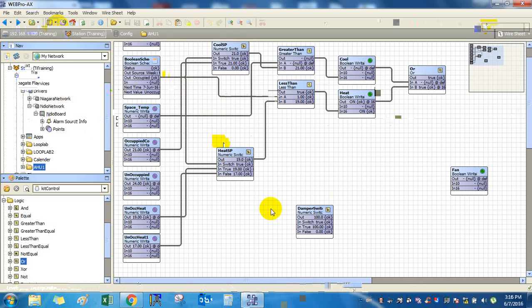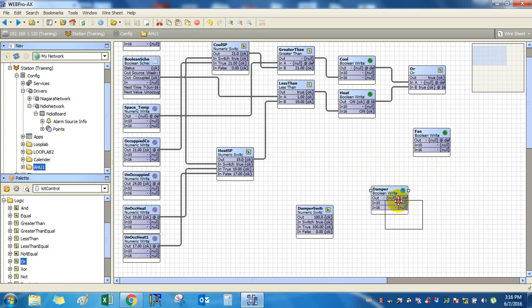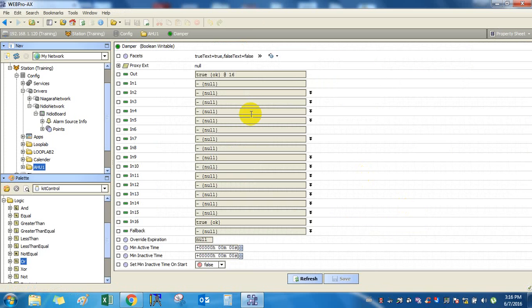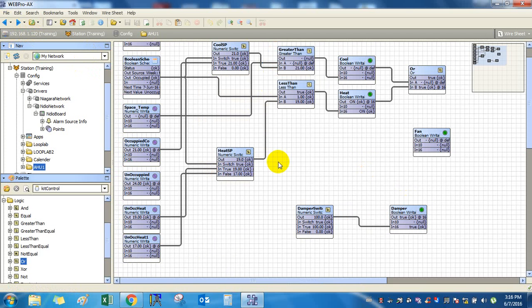Then add another numeric writable point. Name it as damper. Link the out slot to its input 16. Double click here and set the facets to %. If you click here in miscellaneous, select % and then min and max value for damper will be 0 and 100. Save.